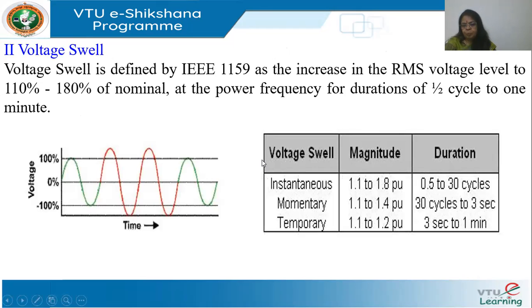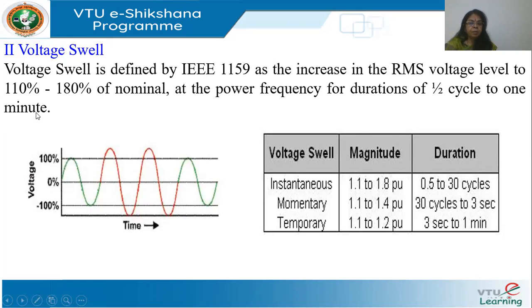The opposite of sag is swell, analogous to over voltage. The IEEE 1159 standard defines a swell as an increase in RMS value from 110% to 180% of nominal, with a duration of only half a cycle to one minute. Subtypes include instantaneous (lasting up to 30 cycles, less than one second), momentary (up to three seconds), and temporary (three seconds to one minute).